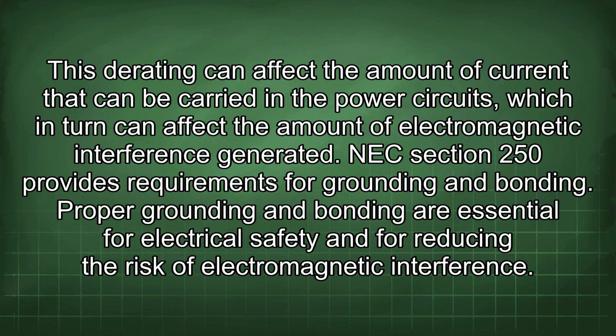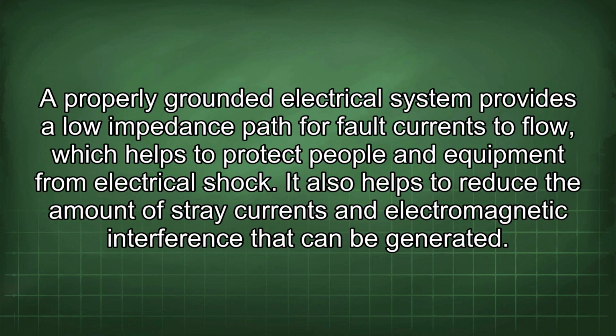This derating can affect the amount of current that can be carried in the power circuits, which in turn can affect the amount of electromagnetic interference generated. NEC Section 250 provides requirements for grounding and bonding. Proper grounding and bonding are essential for electrical safety and for reducing the risk of electromagnetic interference. A properly grounded electrical system provides a low impedance path for fault currents to flow, which helps to protect people and equipment from electrical shock. It also helps to reduce the amount of stray currents and electromagnetic interference that can be generated.